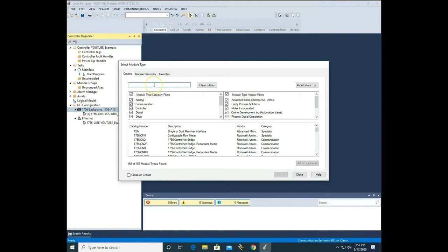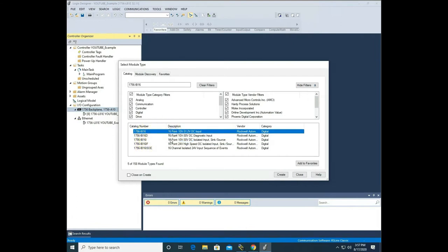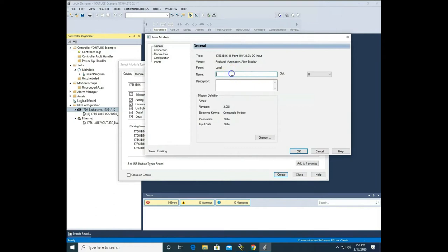Or I can come up to this box, hit Control+V to paste, and it brings up my cards. Mine is the first one. You need to be sure if you've got a 16D or isolated inputs or high-speed — be sure to add the correct card, because it will not work if you add the wrong one. Mine is just an IB16, it's an older card, so I'm going to hit create. It asks me to name it — I'll just name this 'input.' The slot is slot 0, so I don't have to change that. The revision automatically comes up as 3.001, which is not right, so I need to change that.